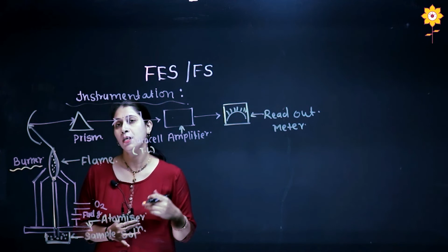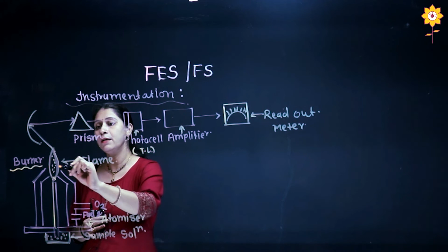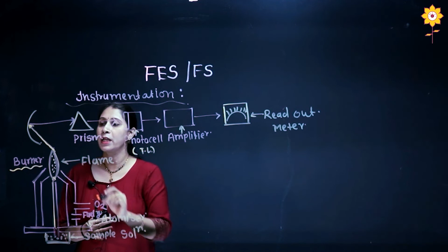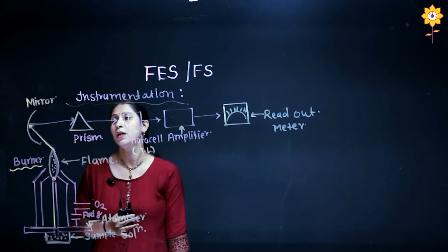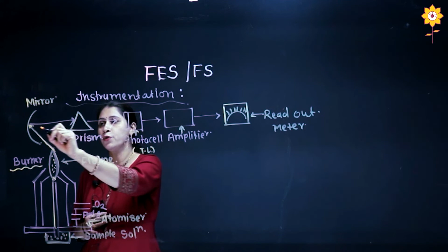Okay, where it forms a mist or fine droplets of the sample. It reaches the flame where the actual heating or burning process starts. Okay, so here we should have a high temperature flame in order to get a good amount of energy. Now when we start the process, the sample gets suctioned and burns inside the flame, from where the rays come out. Now the second part is our collimating mirror. Whatever rays pass from the flame get collimated or focused onto the mirror.